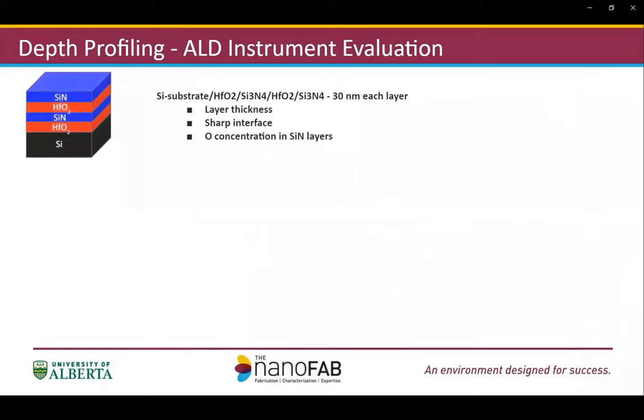Depth profiling analysis is one of the major applications on the VP3 system. We configured two sputter guns: mono-argon and GCIB. I'm going to show two examples done with the mono-argon sputter gun. The first sample is the analysis of an ALD film stack, which is actually part of an equipment evaluation for an ALD tool acquisition for our cleanroom. A test sample of silicon nitride and hafnium oxide film stacks were made on a silicon substrate, each layer about 30 nanometers in thickness. The evaluation focus is on layer thickness, sharpness of the interfaces, and most importantly, the oxygen concentration in the silicon nitride layer.